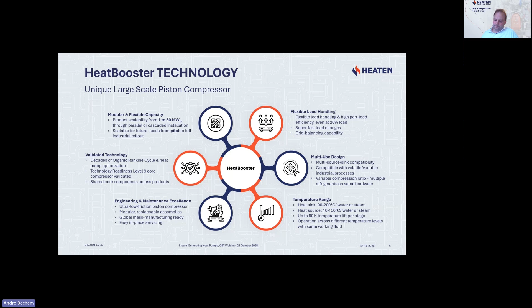With this modular system, we can also enable redundancy. When we would, for example, install 5 or 6 heat pumps, we would not switch one off. We would run all of them at 70 or 80% part load, in our sweet spot, where we have even increased COP and efficiency. For maintenance or redundancy reasons, we can still ramp the others up. That's really our philosophy: installing multiple machines on site.